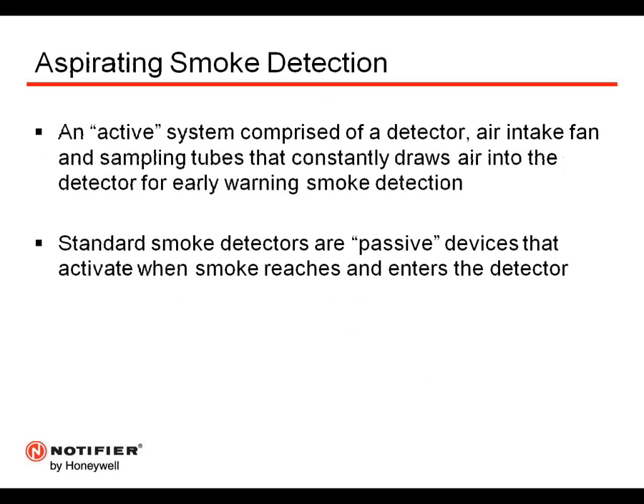Hello, everybody. First, I'd like to start off by giving a broad definition of aspirating smoke detection. Aspirating smoke detection is an active smoke detection system which uses a network of pipes to continuously sample air into the detection chamber, so we're always looking for smoke, whereas a standard spot detector is a passive detection system which requires smoke to come to the level of the spot detector in order to activate.